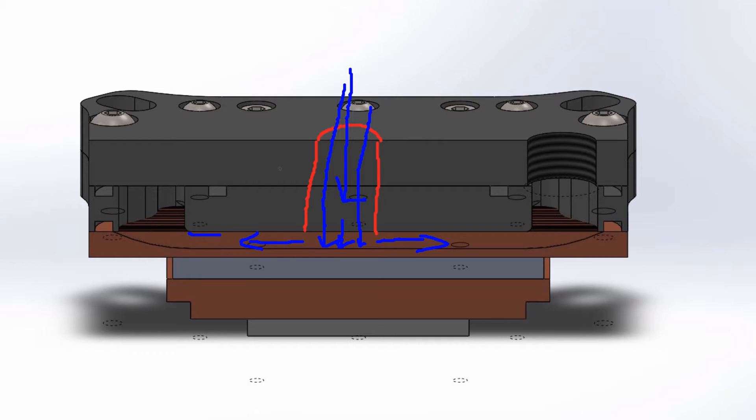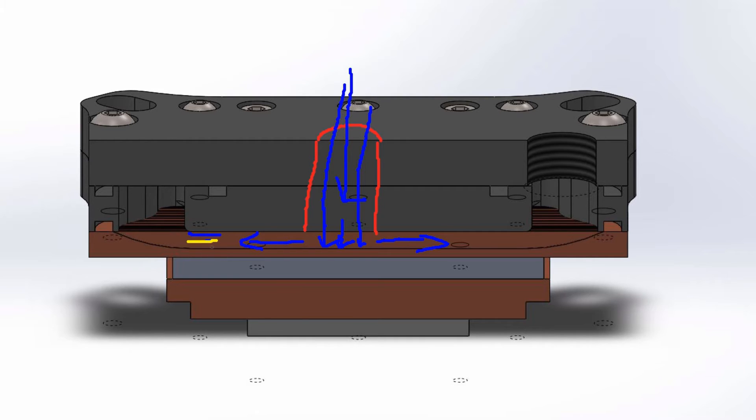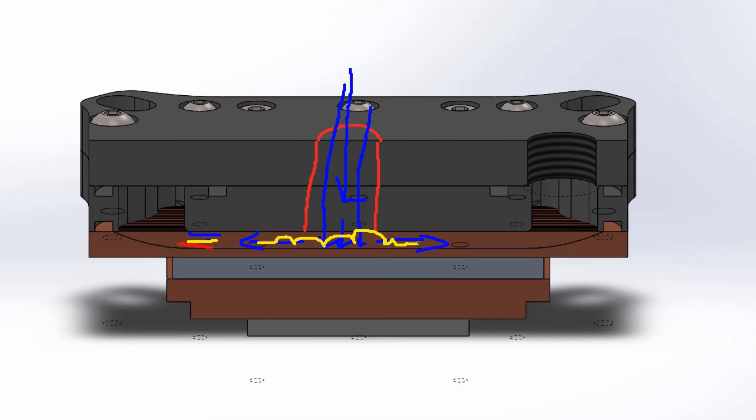Because as we've talked in the past, the water up here will be the coolest, the water in the middle will be medium temperature, and the water along the bottom will be the hottest. And it's hard to get this mixed, but this here forces that to be mixed up and creates an average temperature. It breaks down the boundary layer down here, which is an incredibly good thing. And that is one of the main benefits of using center firing.